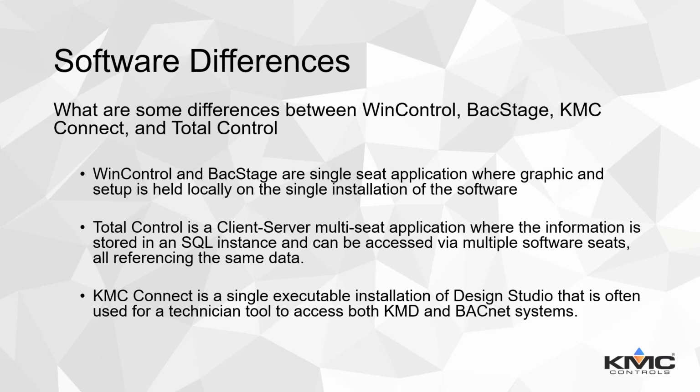What you cannot do is set up the graphical pages. You can't publish graphical pages. Those things are going to be restricted to the TotalControl application, but you can make a lot of configuration changes on BACnet. You can still do application deployment through our libraries. You can still do backups and restores. It has a lot of features of our Design Studio component, but it just runs in a single executable. And again, it has to be running to be working. So it's not a services-based solution like TotalControl.